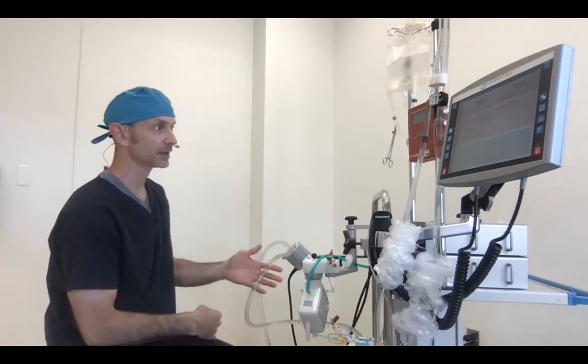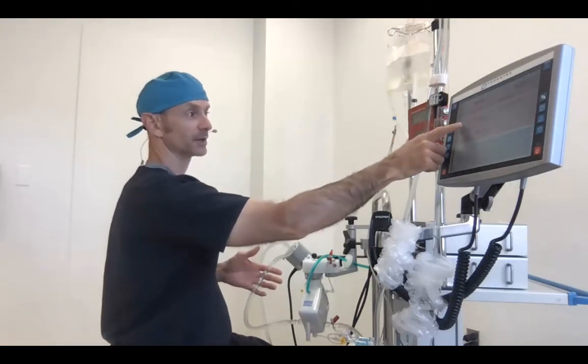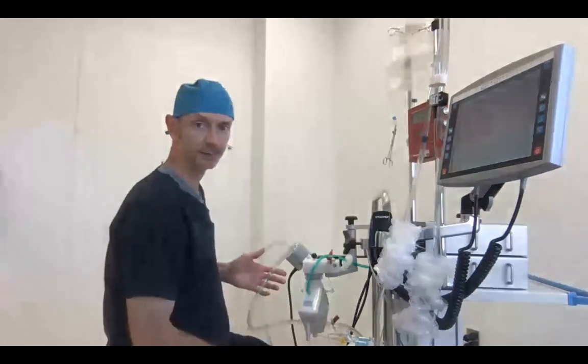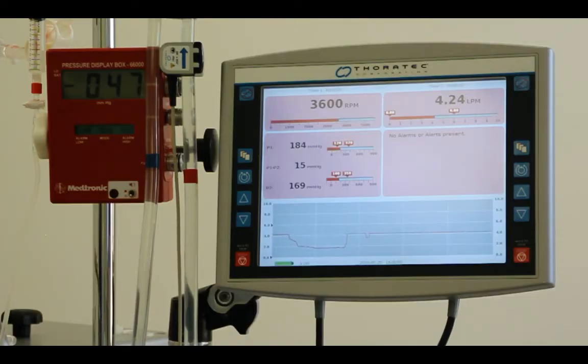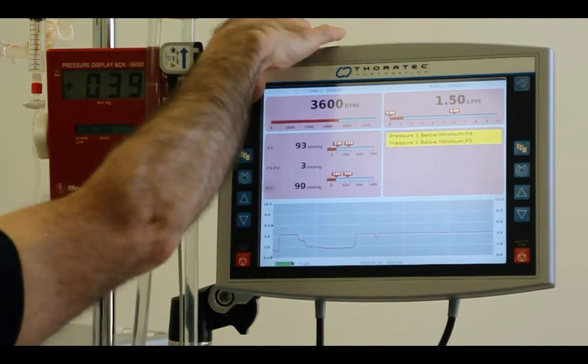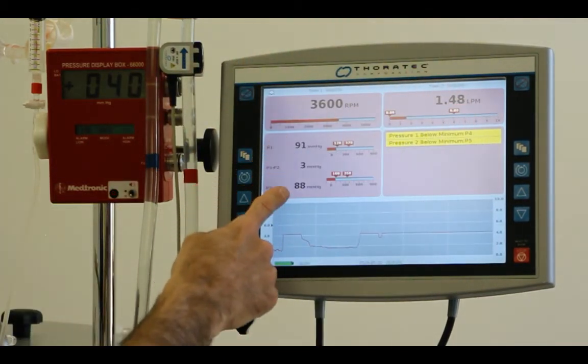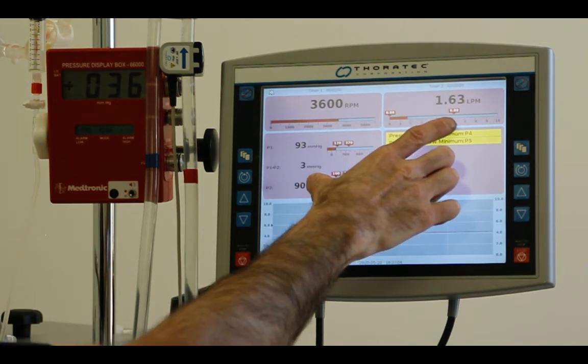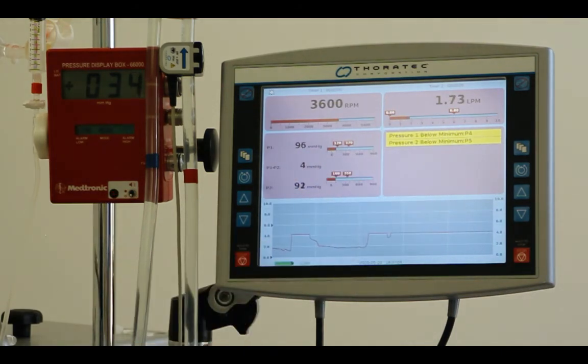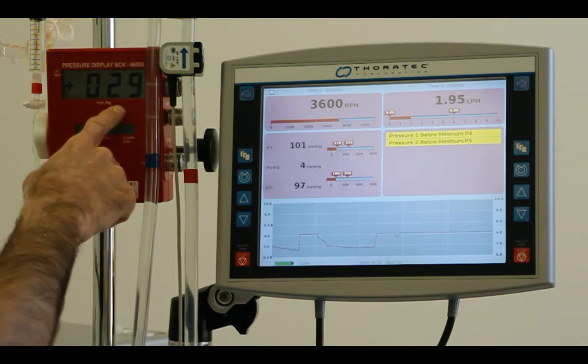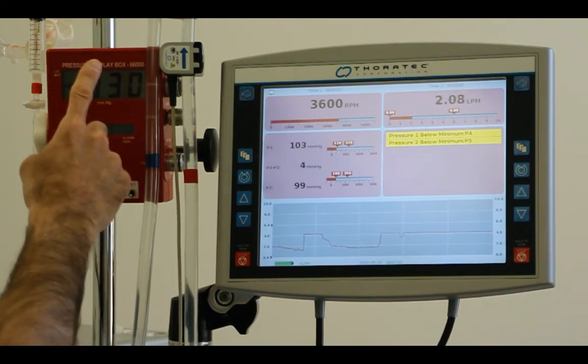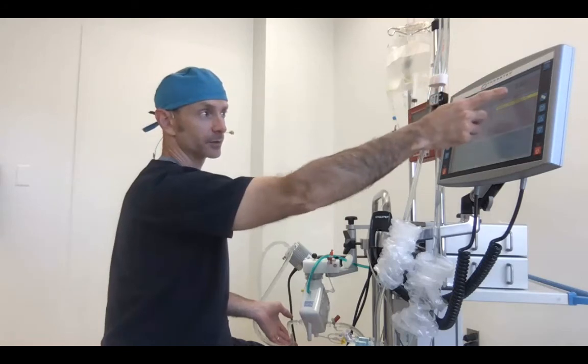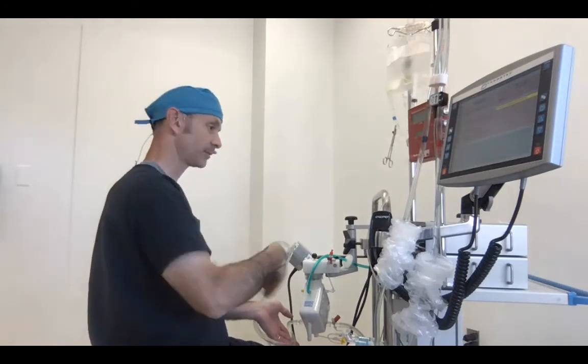Now I relieve the kink. This becomes more negative. These become more positive, and the pressure goes up. If we put a kink down here, the other end of that tubing, right here at the inlet of the oxygenator, flow comes down, pressures come down. That makes sense. It tells you there's no problem after the oxygenator. And the venous line pressure, if you had that, it goes up while the flow comes down. Says there's not a problem in the venous line.